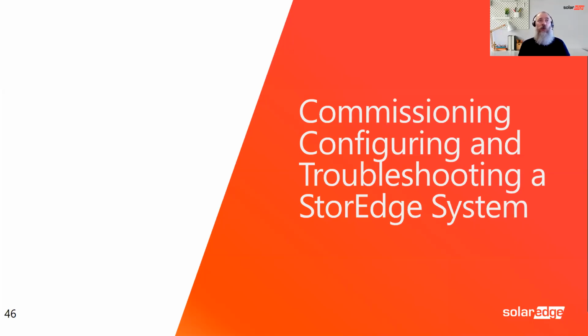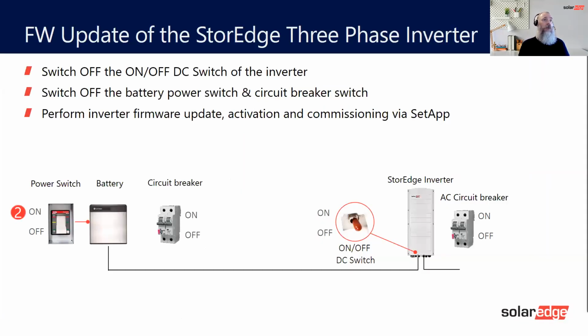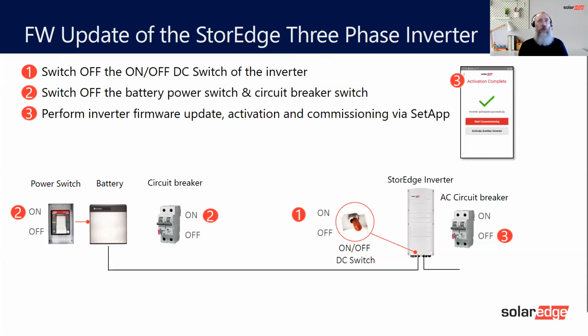Commissioning and configuring the troubleshooting. So we'll look at this. Hopefully you shouldn't have any major issues. The most important one is the update, to make sure that the inverter and the battery both update themselves, and you just need to follow what's in the manual to make sure that everything is off, the battery's off, the inverter's off, and allow it to perform its update. Once it's performed the update, you can then switch on everything and start again.